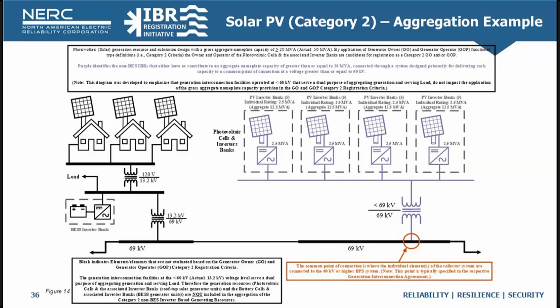In addition to that, we've depicted battery energy storage inverter banks connected at 13.2 that are also there to serve load and are not there to be aggregated and stepped up to the 69 kV level. So the rooftop solar generation resources and the battery energy storage resources are not included in the aggregation of the Category 2 non-BES inverter-based generation resources on the right, connected at 13.2, based on the fact that the interconnection facilities have a dual purpose of aggregating generation and serving load.